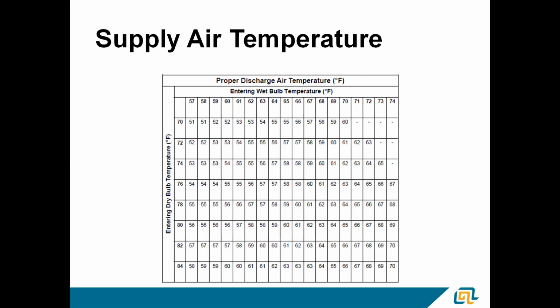When I was creating another slide a little further on, I found that Emerson has an app called Check Charge, and it's actually a really slick little app. It'll do the superheat calculations for you if you're charging a piston or a restrictor. It'll do the subcooling calculations for you if you have a TXV, and it will also do proper discharge air temperature. You still have to punch in your parameters, the dry bulb temperature, the wet bulb temperature, and what temperature you have coming off the evaporator. And it will tell you whether or not you need to add more air or reduce the amount of air going across that. Pretty slick little app. I kind of happened onto it. It's Emerson Check Charge. As you know, Emerson, Copeland, White Rodgers, it's all the same company, so it comes with quite a bit of years of experience behind it.